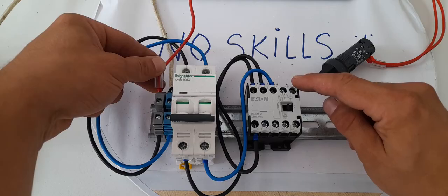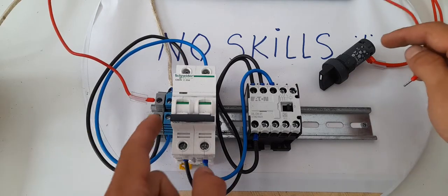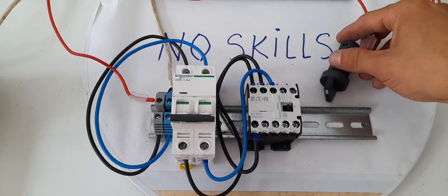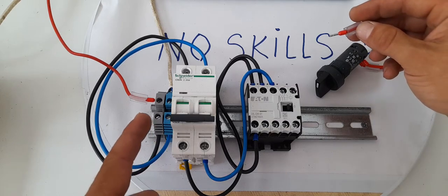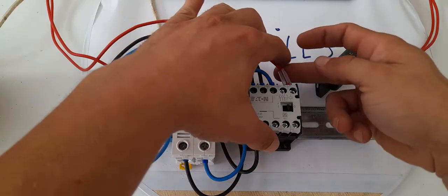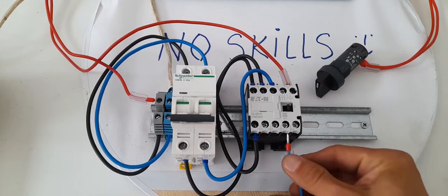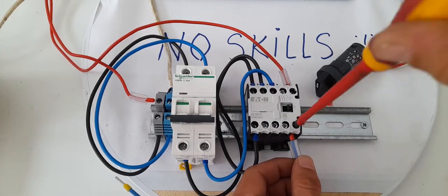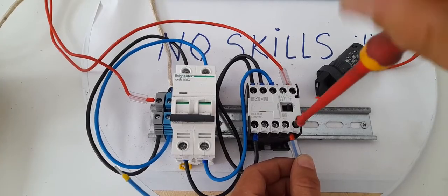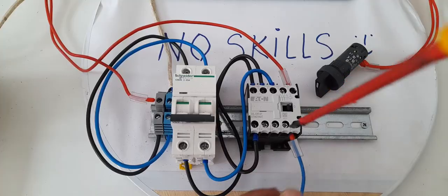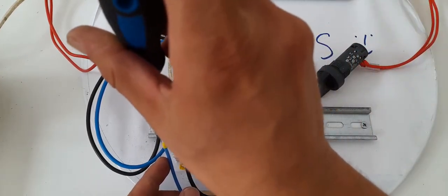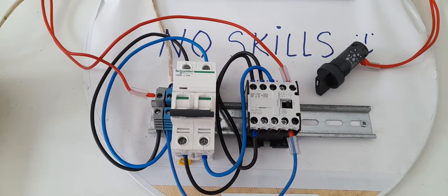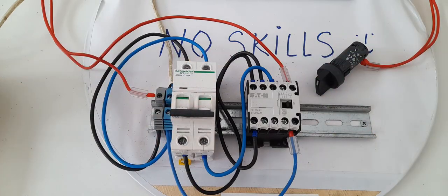And the exiting of the button we're gonna connect it to the A1. Alright so we have connected the one terminal of the switch, doesn't matter which one, we're gonna connect it to the live to the entrance and the other one we're gonna hook up to A1. Alright and now to complete the circuit we're gonna put a blue wire through the A2, the terminal of the coil of the contactor, to anywhere to a neutral connection. We're gonna connect it here and there you have it.